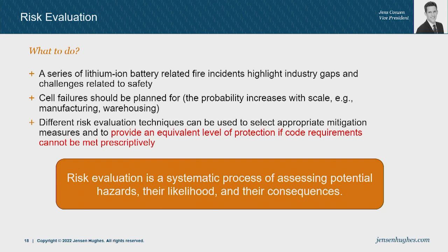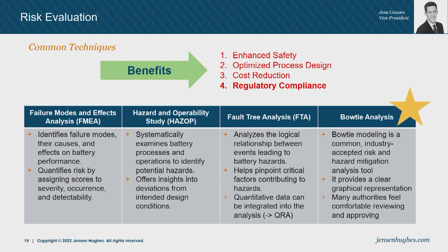We found that is important because we actually did have a number of fire incidents now in large facilities that handle lithium-ion batteries. The question is really not if I have a fire, the question is when will I have an incident I need to deal with? It just has to do with the huge amount of batteries being moved through these facilities. It's a probability game in a way. We now have facilities that store upwards of 10 million cells. There are for sure going to be a handful of bad cells in that storage arrangement. So we need to plan on cell failure, and we need to have something that we can demonstrate to the company, the workers, and the authorities that the approach is safe.